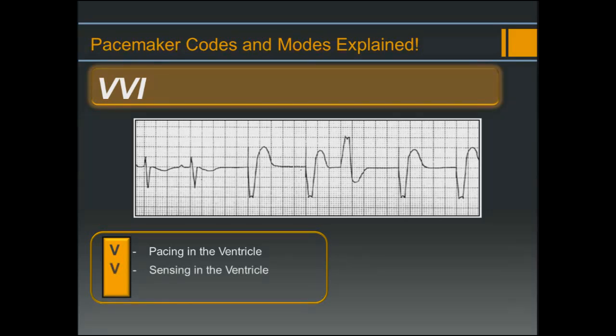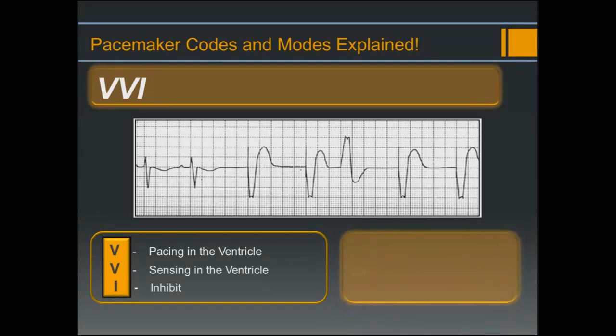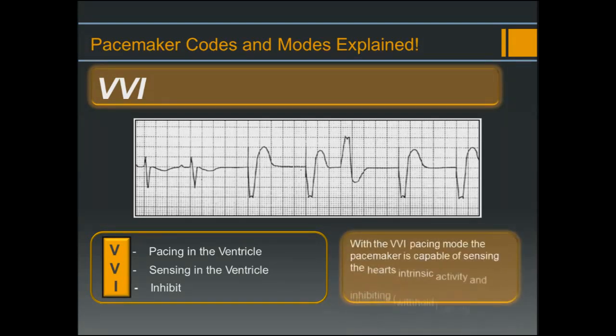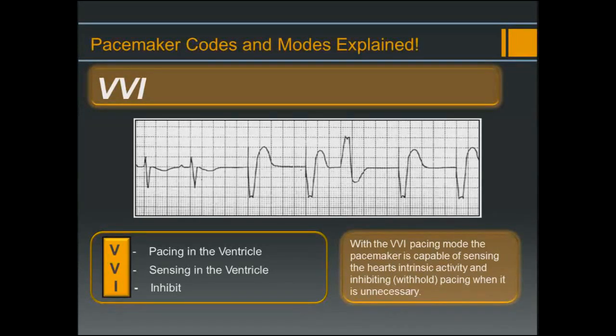VVI pacing mode: we now have pacing in the ventricle, sensing in the ventricle, and a response to sensing that will be to inhibit. With the VVI pacing mode, the pacemaker is capable of sensing the heart's intrinsic activity and inhibiting or withholding pacing when it's unnecessary.